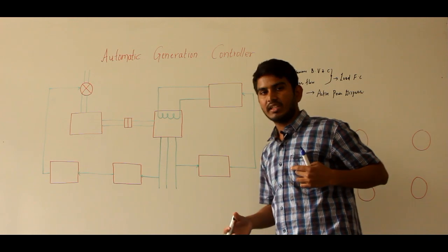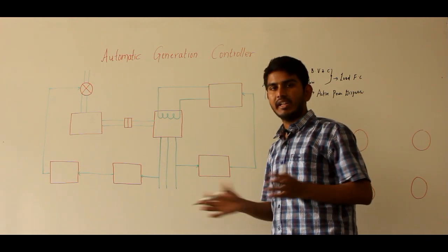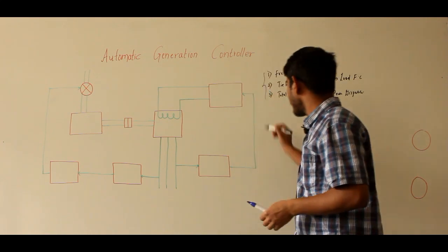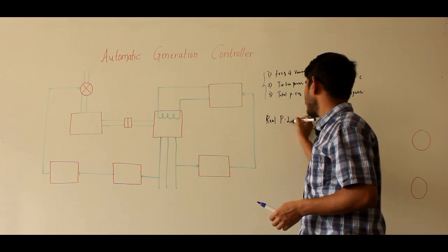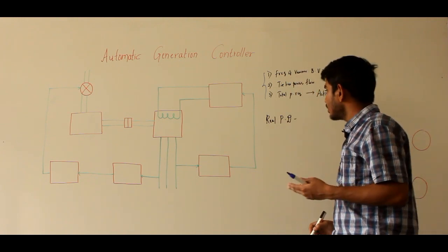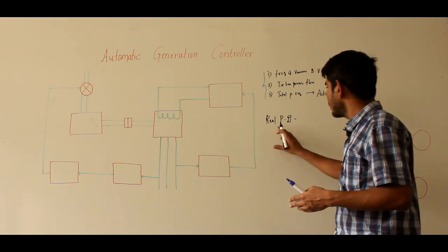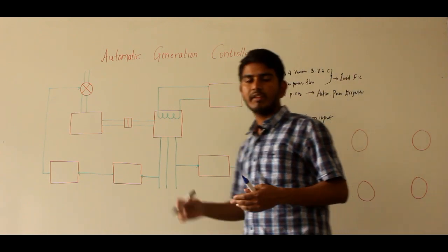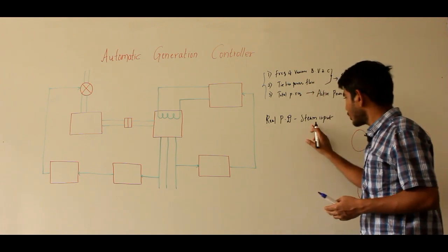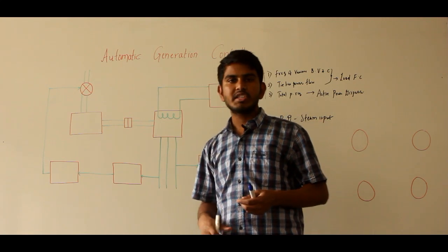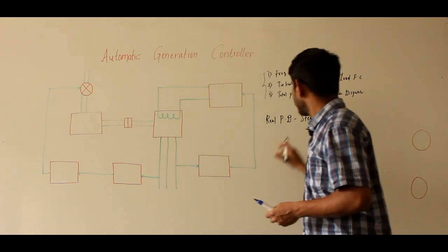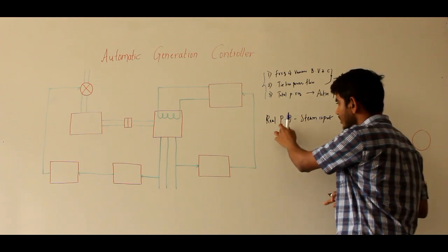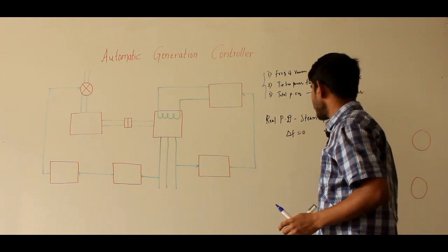Real power demands will be varying. As these demands vary, bus voltage and frequency will also vary. In order to match the real active power generation with the active power demand, we can adjust the steam input. The steam input to the turbo generators — or water input for hydro generators — must be continuously regulated so that real power generation will match the real power demand. When real power generation matches real power demand, the change in frequency will be equal to zero.